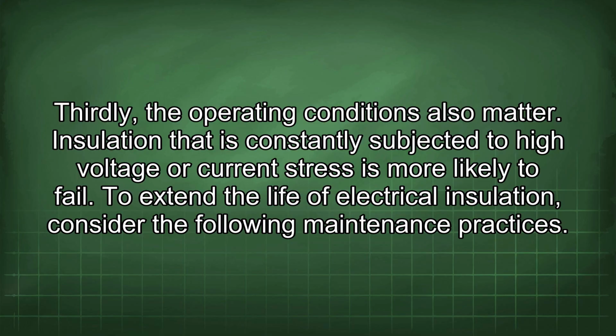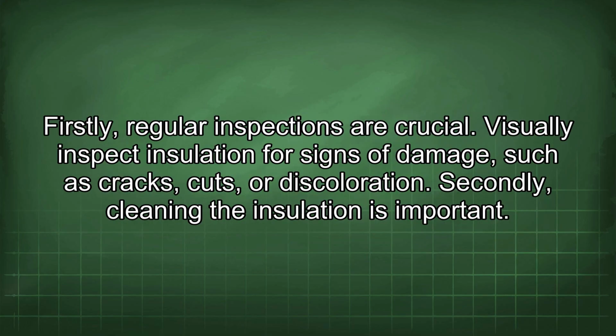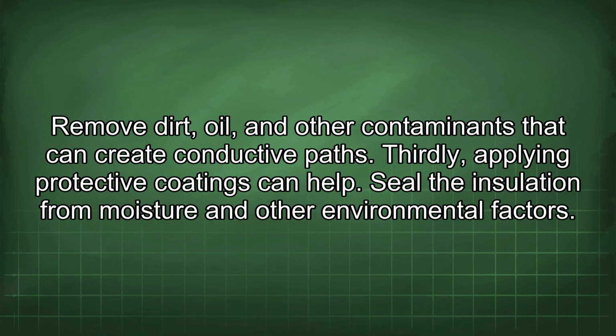To extend the life of electrical insulation, consider the following maintenance practices. Firstly, regular inspections are crucial. Visually inspect insulation for signs of damage, such as cracks, cuts, or discoloration. Secondly, cleaning the insulation is important. Remove dirt, oil, and other contaminants that can create conductive paths.